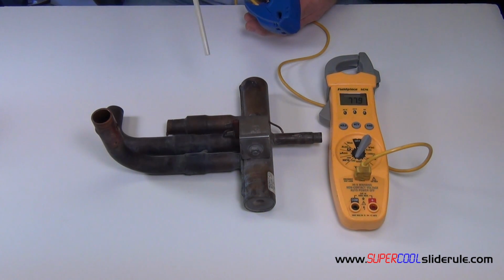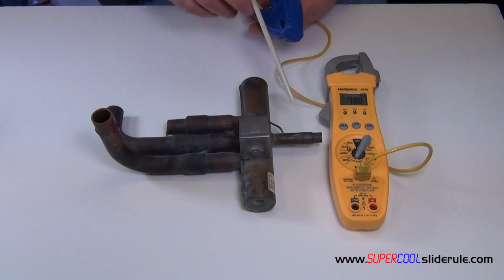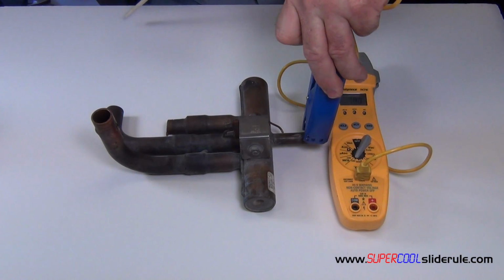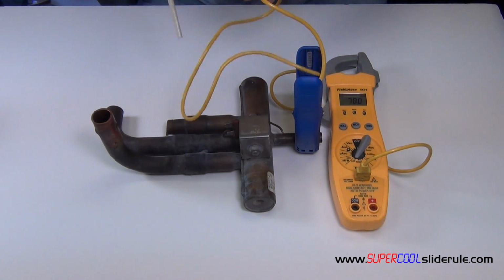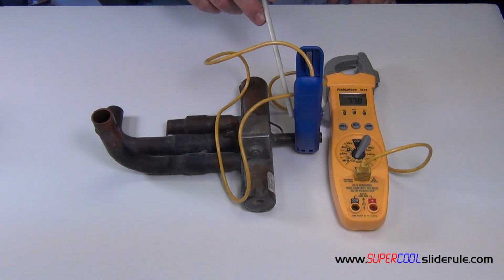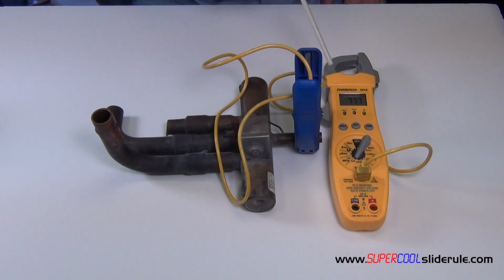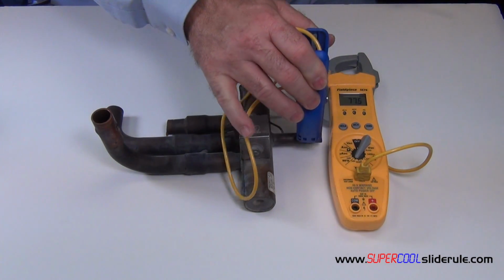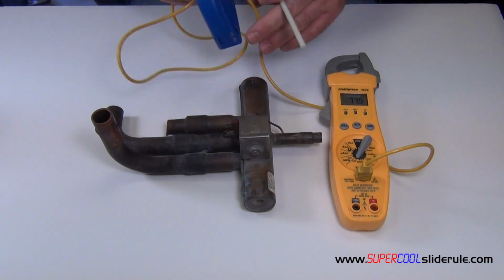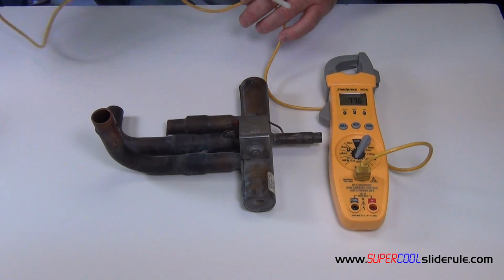First, with the unit running, we allow it to run for 5 to 10 minutes for it to stabilize. Once it is stabilized, we start by checking the temperature of the hot gas line as shown here with the temperature clamp. Once this temperature has stabilized, we test the tubes on the bottom.